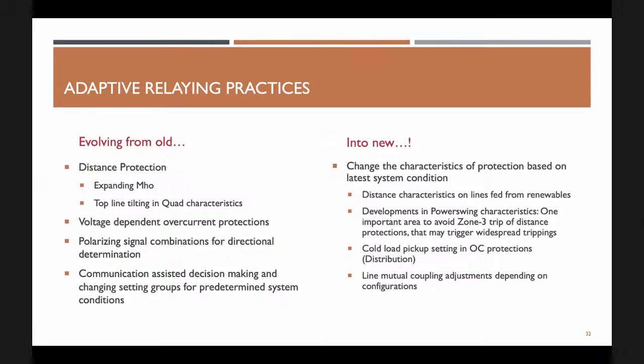If you remember, in distance relays we used to call it the expanding Mho characteristic, and the quad characteristic, where the top line would tilt to adjust for resistance depending on whether the load flow was in the forward or reverse direction. We also used to have voltage dependent overcurrent protection. All these things had a certain element of adaptivity built in automatically. Even in the static protection days, we used to have it.